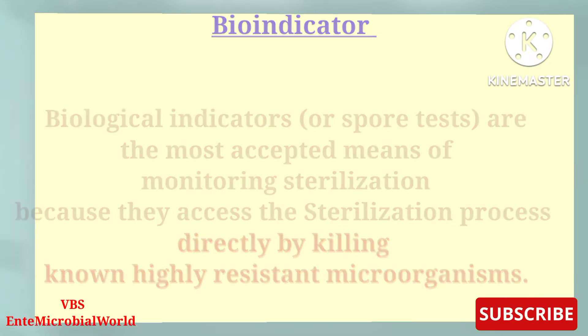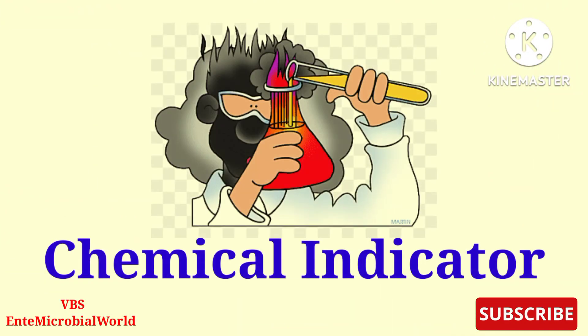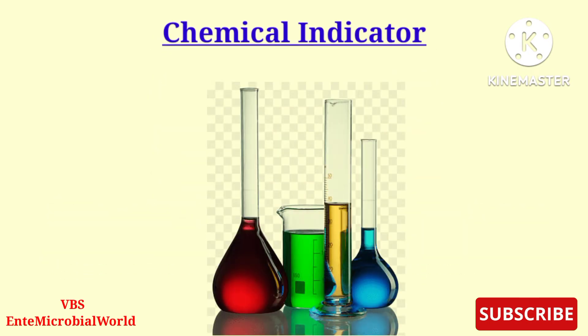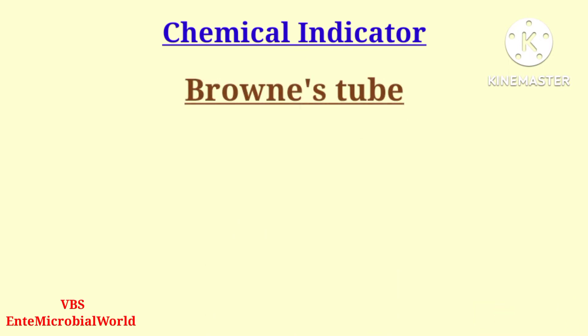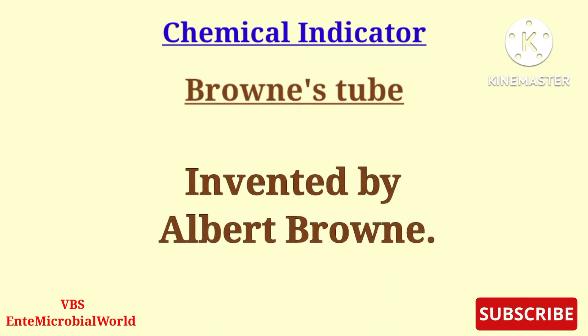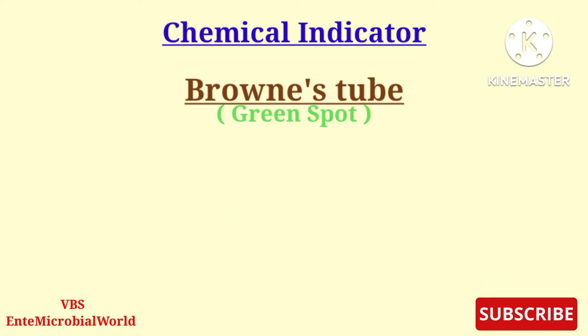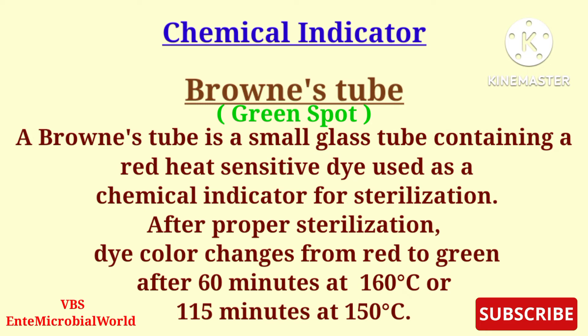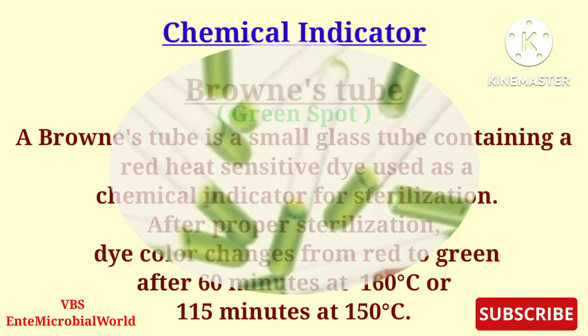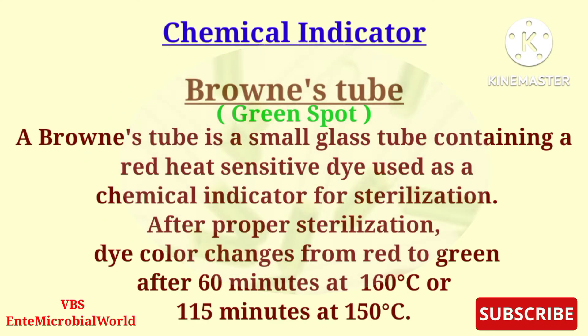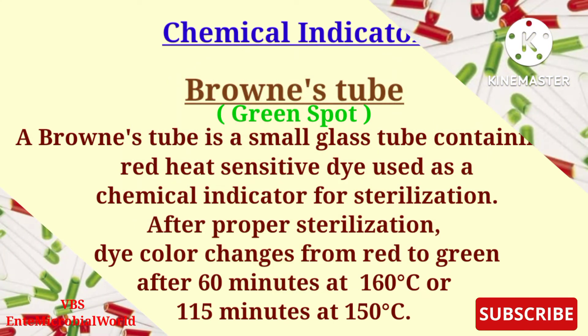Next, we are going to see about chemical indicators, where chemicals are used as an indicator. Brown's tube is a small glass tube containing a red heat-sensitive dye used as a chemical indicator for sterilization. After proper sterilization, a green color is produced — after 60 minutes at 160 degrees Celsius, or 115 minutes at 150 degrees Celsius.